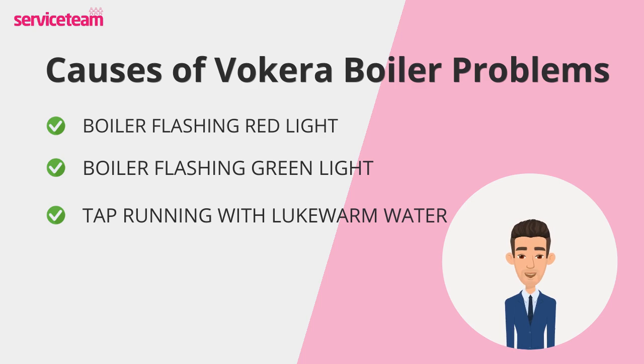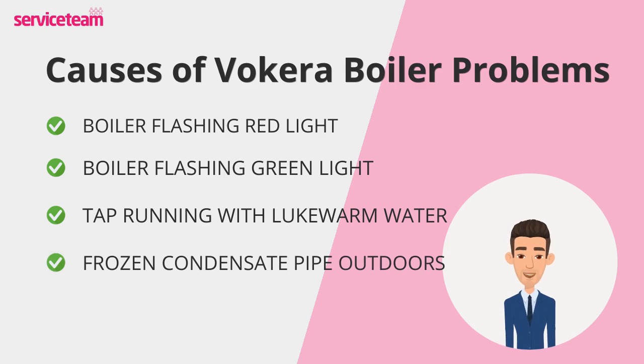In colder months, you might see error codes 92, 93, or 95, which usually point to a blocked or frozen condensate pipe. You can try carefully thawing it with warm water, but if the blockage is persistent, it's best to get professional help to prevent damage.